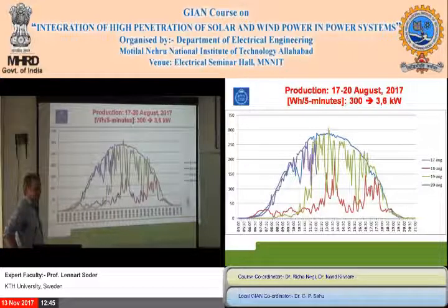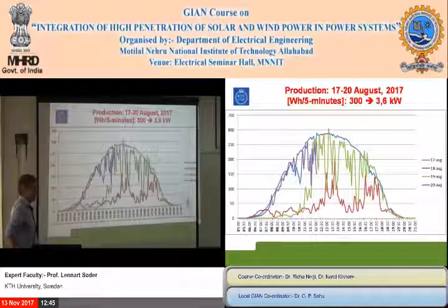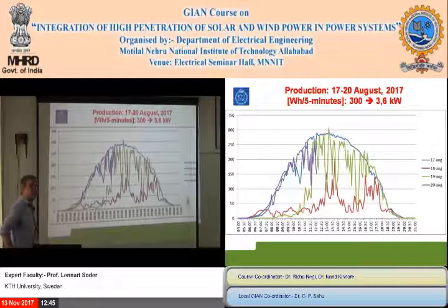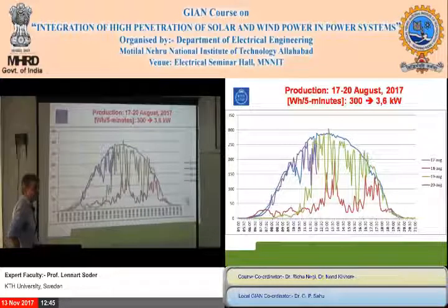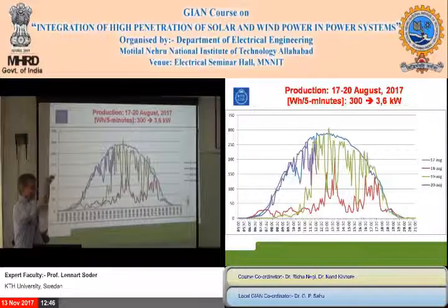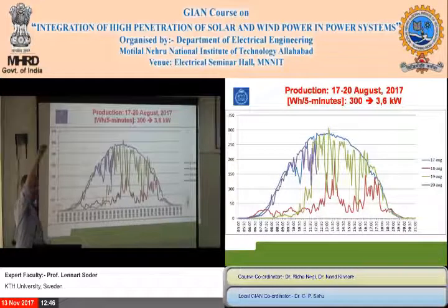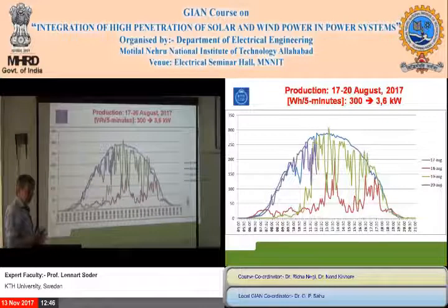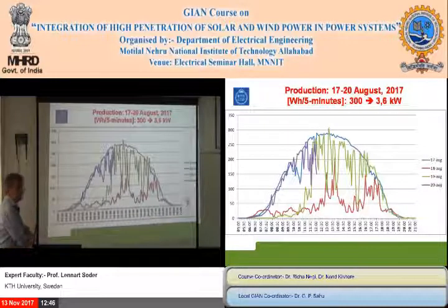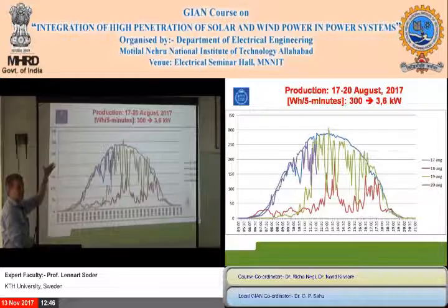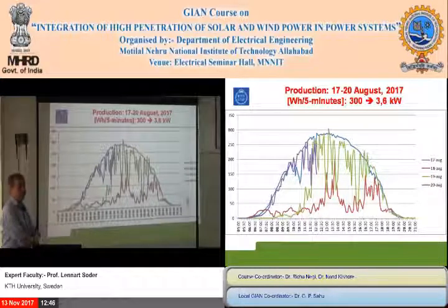We have moving clouds. And this of course has a big impact on how solar power is working in distribution grids, at least in Sweden. You can have clear sky, and then 2 minutes later it's very black. And then after 2 minutes, it's clear sky again. And a black cloud is taking away around 95% of the radiation.